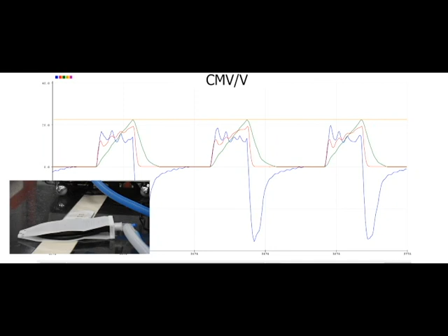Now here you can see in the graph that we have three different plots running together, and the first one, which is blue colored, is for the flow. You can see that during inspiration the flow is rising up, and during expiration the flow is going downward, becoming negative. In each expiration and inspiration cycle, you can see the same phenomenon repeated based on the setting of the ventilator. At the same time, the red curve shows the pressure of the airway, which maintains just like a square pulse. And the third one you can see is the tidal volume. We have set tidal volume for 450 cc, so you can see the tidal volume is getting 450 cc over here.